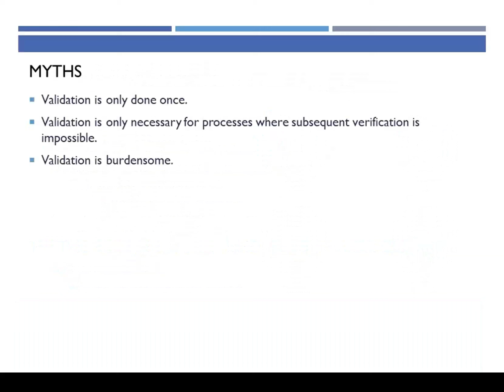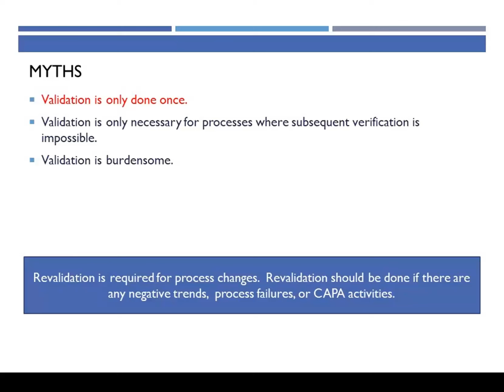If you're changing your process, revalidation is explicitly required. But also, remember, you're supposed to monitor your process over time. And if you see any changes, any drift, any negative trends, any process failures, you need to review, evaluate, and revalidate. If you've had any corrective and preventive action, you need to review and revalidate. It's not a static thing.